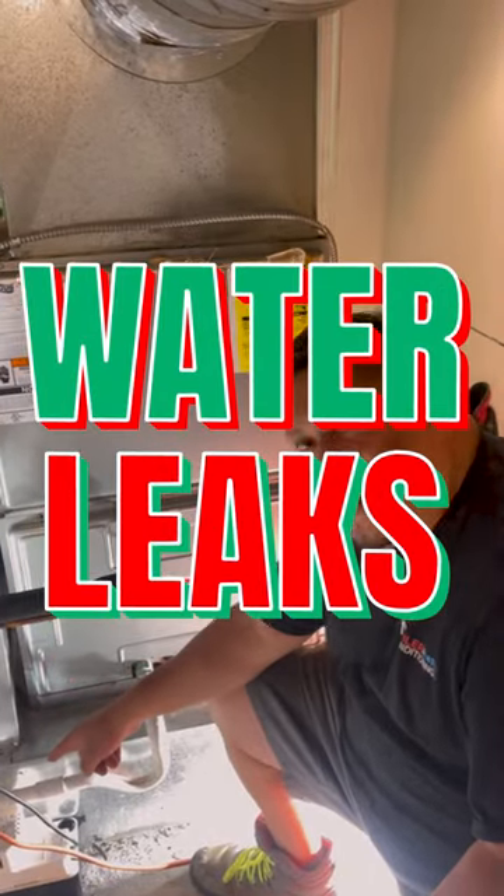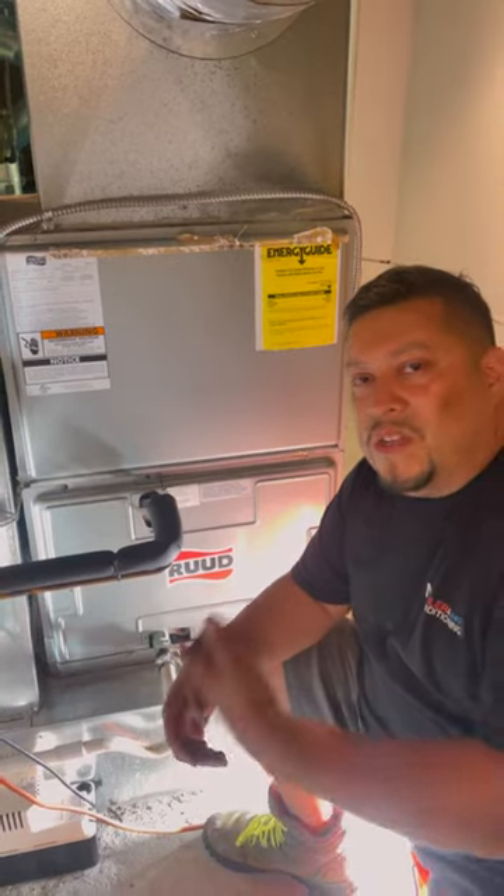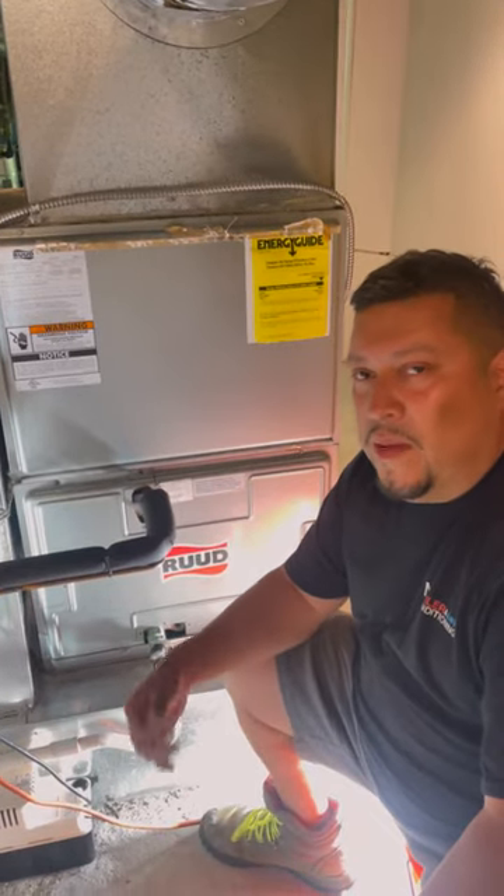When the water was leaking to the condensate pump, it was also overfilling. Why? Because the pump was bad — it was on, I felt it — it was just not pumping.